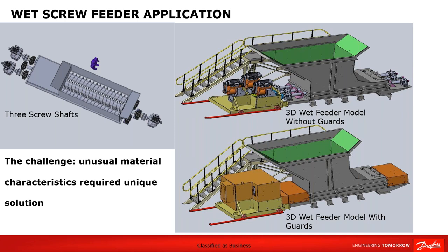The way this operates is that the follower effectively mirrors the master encoder. And I'll come to the next slide, where I'll point this out on a scope reading. So if the master screw shaft runs at a certain speed, the follower MCO card monitors that speed and matches it so that the follower shaft is running in sync with the master reference. If the application does stop in an alarm state, all the motors will coast to a stop and the follower shafts will be out of sync.